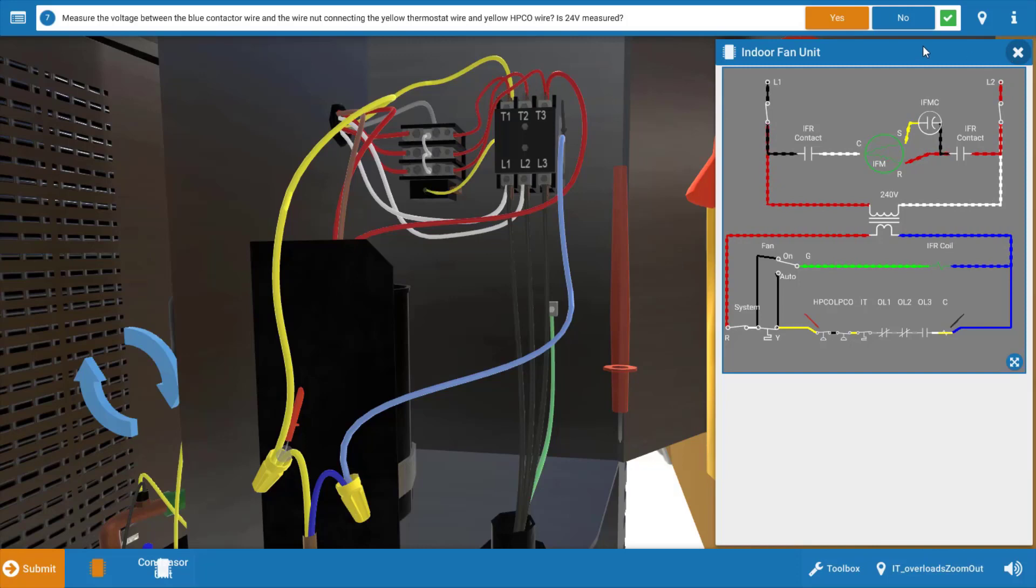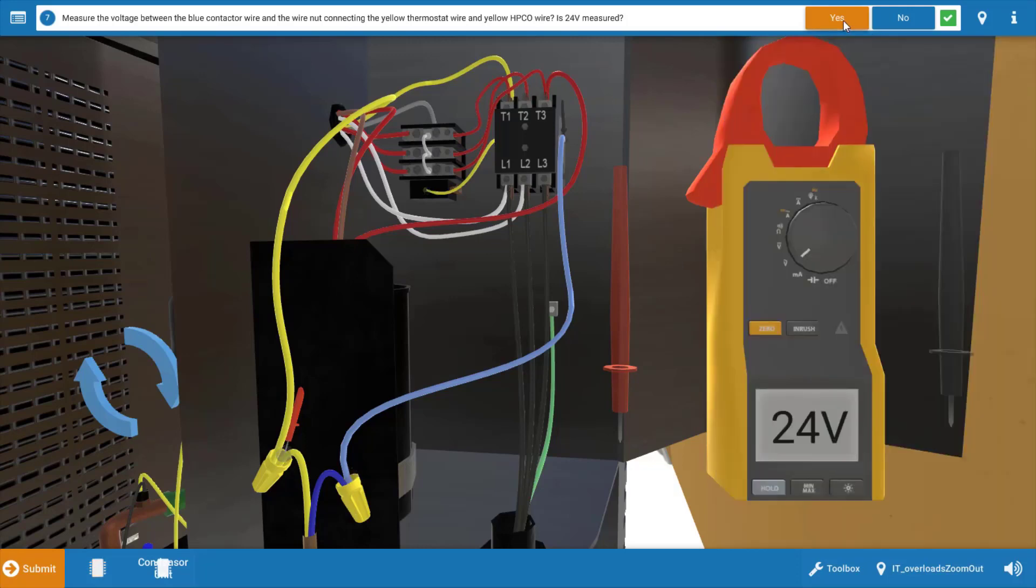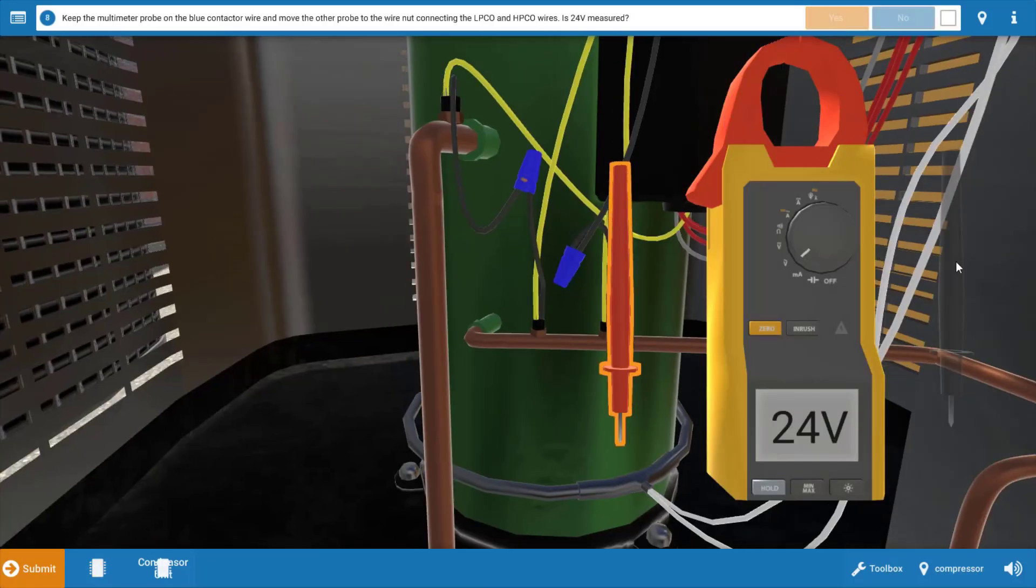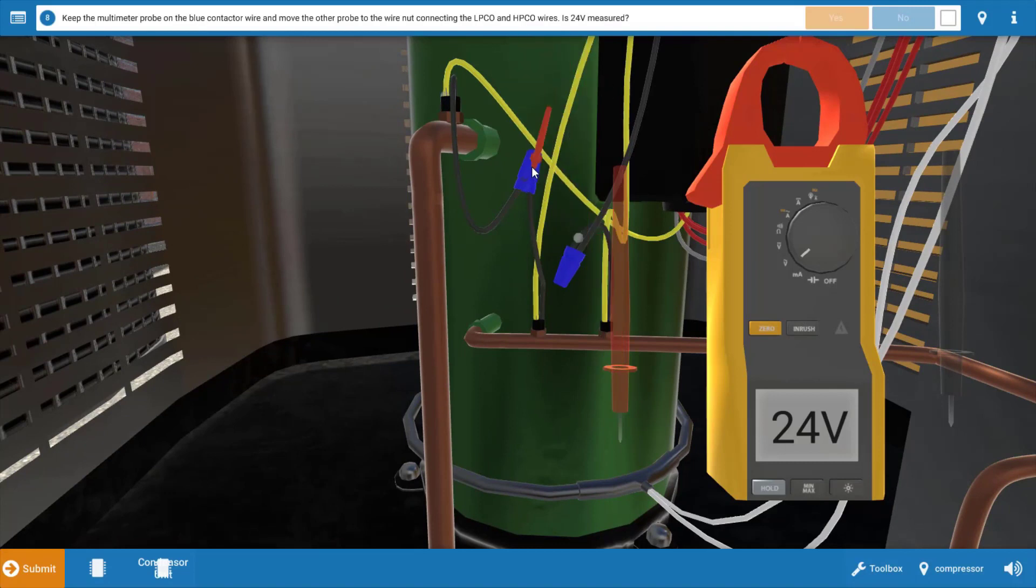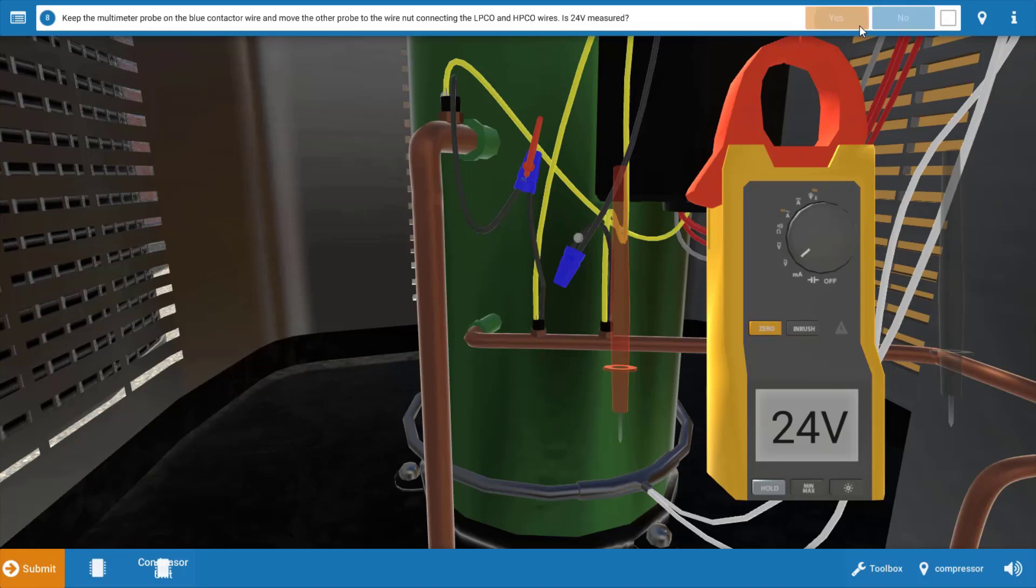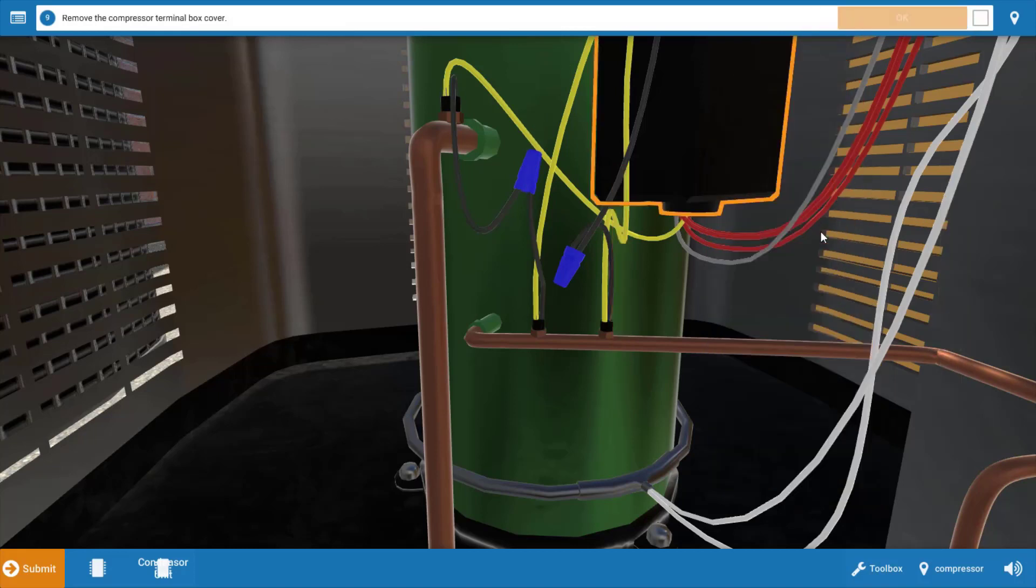Our next step after clicking yes on the procedure guide is to check for power coming out of the high pressure cutout. We can do this right at the blue wire nut here, and we have 24 volts, so we're going to click yes and our high pressure cutout checks out.